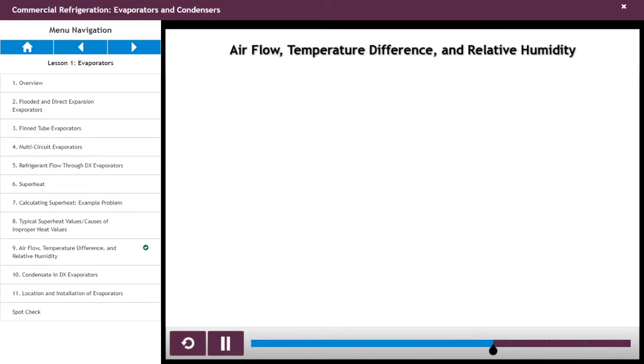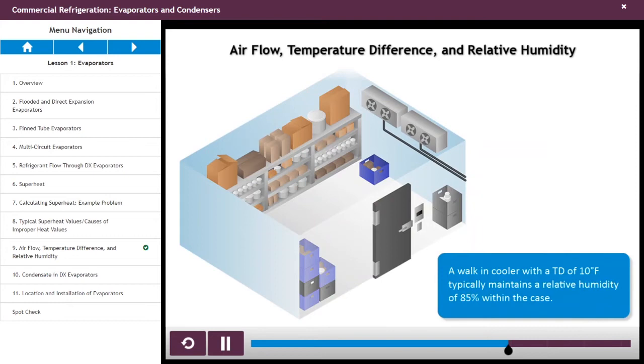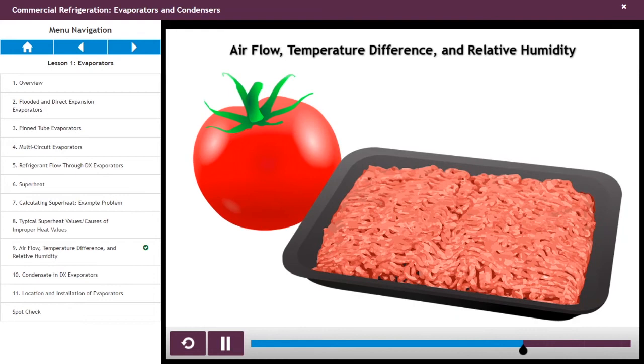A walk-in cooler with a TD of 10 degrees Fahrenheit typically maintains a relative humidity of 85% within the case. The high humidity is good for storing meat and produce, so it does not get dried out.